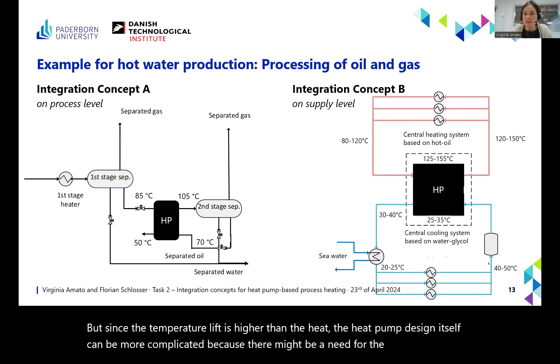The heat pump can also be integrated on a supply level, where it supplies heat for the central heating system with a dedicated heat transfer fluid, usually hot oil on the heating side and a water-glycol mixture on the cooling side. This integration requires higher supply temperatures, and it's an easier integration in which you can use more standardized heat exchangers. But since the temperature lift is higher, the heat pump design itself can be more complicated, because there might be a need for different refrigerants and a cascade system.